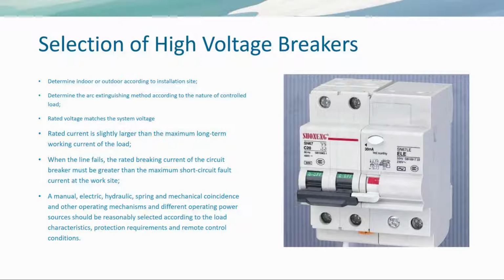Let's look at how to select and operate circuit breakers. 1. Selecting circuit breakers. First of all, we need to determine the installation site of circuit breakers as indoor or outdoor. Then, determine the arc extinguishing method, according to the nature of controlled load. Usually, for loads that require frequent operation, more oil, vacuum or magnetic blower circuit breakers can be used, while for loads that are not frequently operated, less oil circuit breakers can be used.